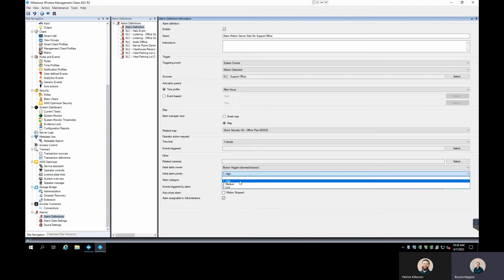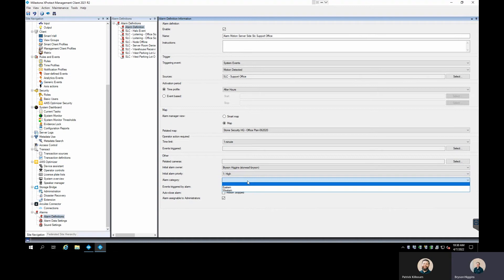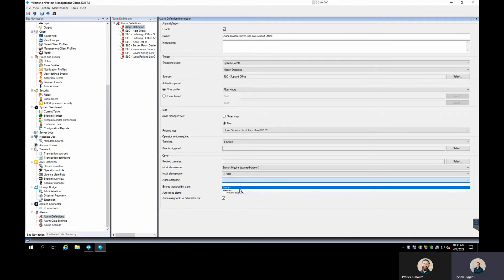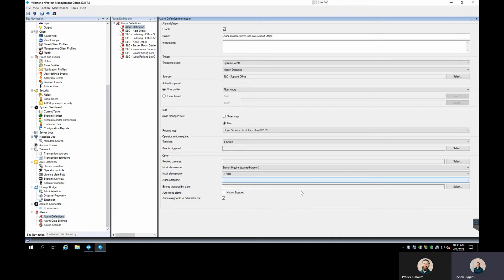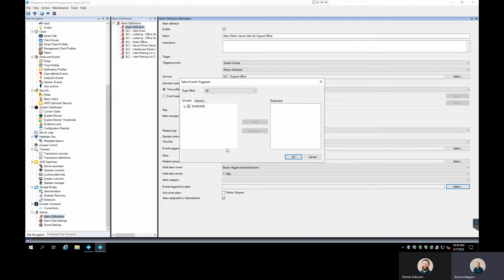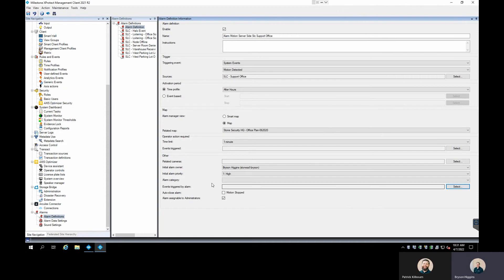We can define the priority level here — the priority levels are configured in alarm data settings, which we'll go over shortly. I'll set this to High. We can also define a category, such as the predefined Eastern or Western categories, which are for organizational purposes in the alarm manager. Then you can specify events triggered by this alarm — when the alarm goes off, other actions can happen: trigger a floodlight, a strobe light, play a message on a speaker, or any output tied into the system.